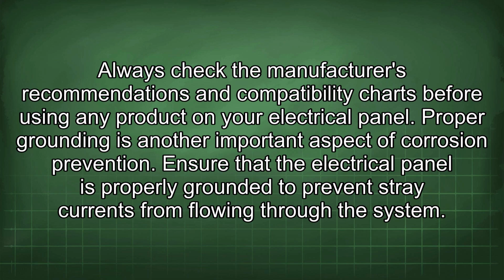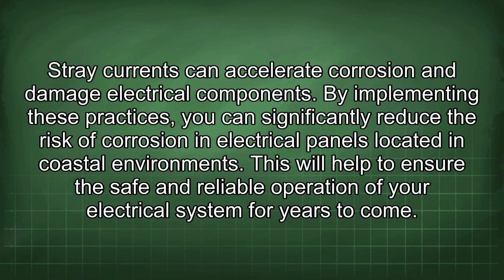Proper grounding is another important aspect of corrosion prevention. Ensure that the electrical panel is properly grounded to prevent stray currents from flowing through the system. Stray currents can accelerate corrosion and damage electrical components.